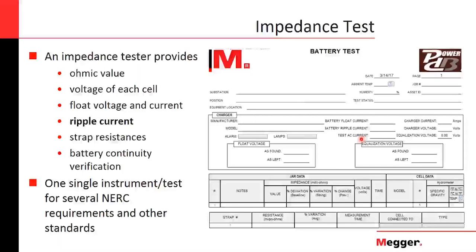You can measure the strap resistances the same way that you were able to measure a voltage drop across the cell. You can measure the strap resistance by measuring the voltage drop across the strap due to this same AC current that you're applying. And the fact that you are injecting a current throughout the system, and you can measure that current anywhere in the battery, in the string, means that you have battery continuity, which is one of the requirements of NERC.